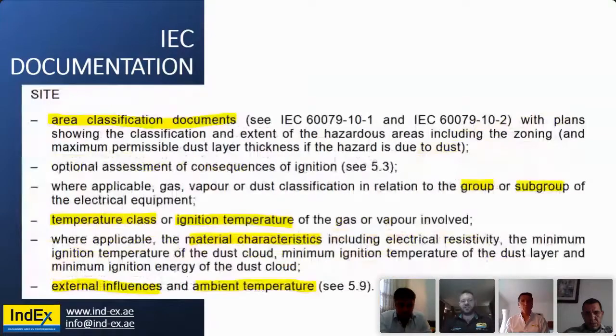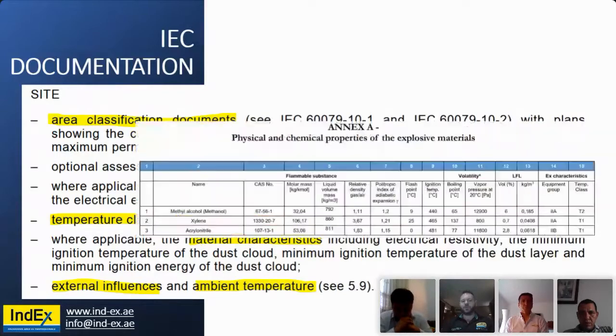What is first done is area classification, defining what gases, vapors, liquids will be there, dusts, what their ignition temperatures are, their material characteristics, any possible external influences such as ambient temperature, any other possibilities that could cause ignition. We then define what those gases are and its relative density, lower flammable limit, gas group, and temperature class. We do this in a very organized method.